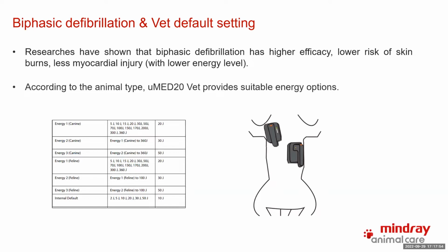For this defibrillator monitor, the most important thing is the technology they are using to do the defibrillation. Another thing is the default setting for the energy, because when we do the defibrillation, we put a lot of energy into the patient to get them back to a normal heartbeat. Research shows that biphasic defibrillation has higher efficiency, lower risk of skin burns, and less myocardial injury. Right now in the market, there is also another technology, monophasic, but monophasic is not as good as biphasic.